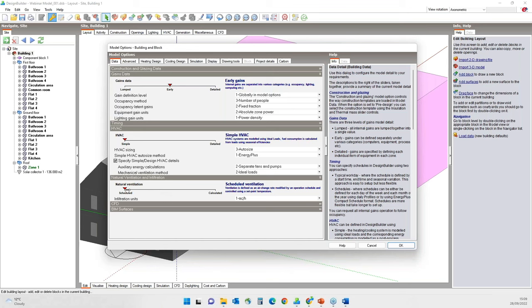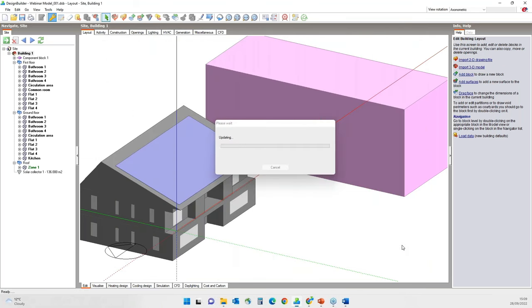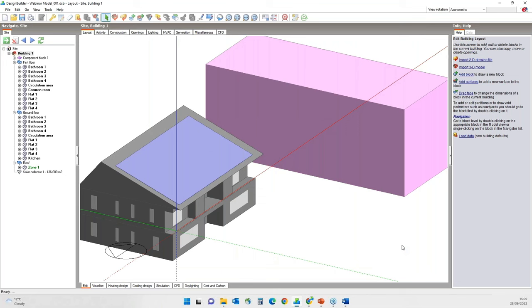The default scheduled option is generally used for early stage modelling and is the fastest and easiest method to set up and run. Infiltration rates can be specified using one of four different units, consistent with local certification requirements or schemes like Passive House. You must ensure you select the correct option for your purpose. I will leave it to air changes per hour. Aspects of a building design that impact natural ventilation are spread across several areas of model data, involving HVAC, activity and construction tasks. I will now go through the steps required in each area to set up a scheduled natural ventilation simulation.